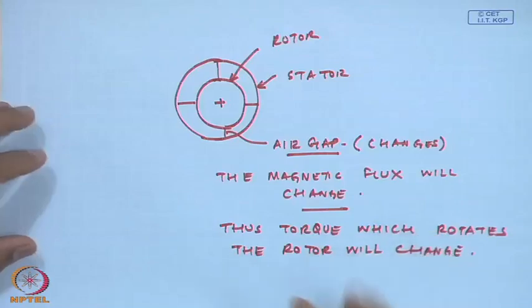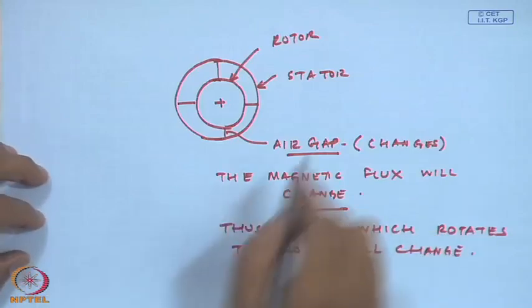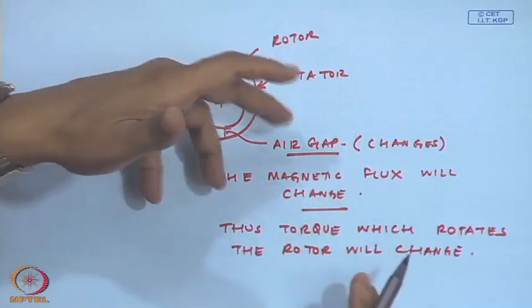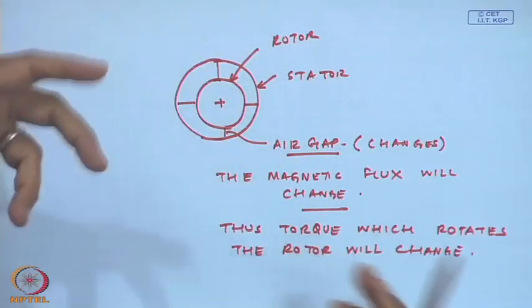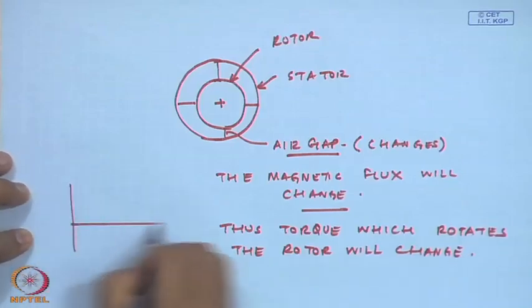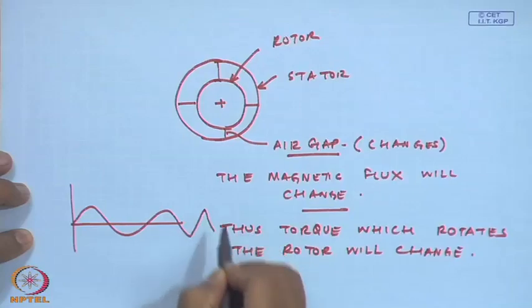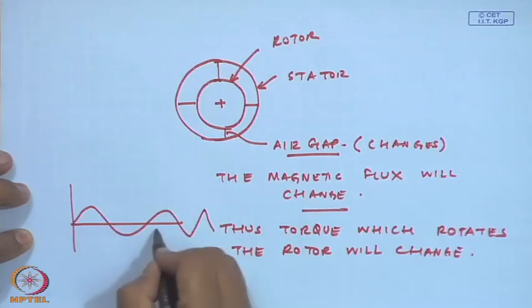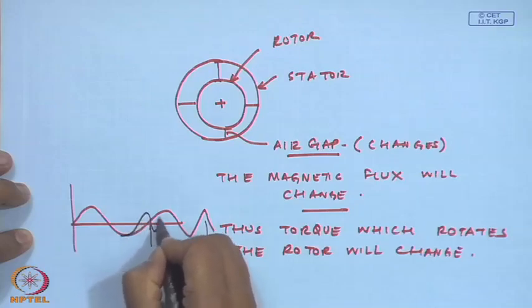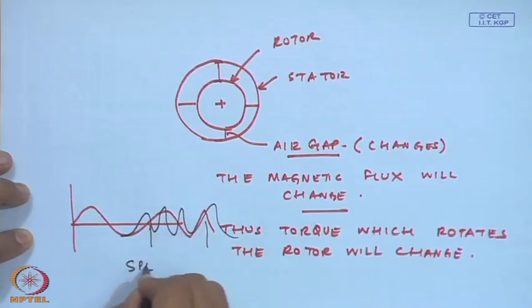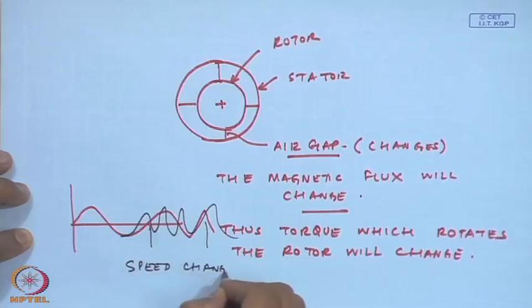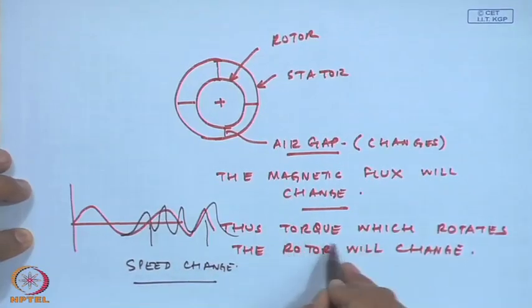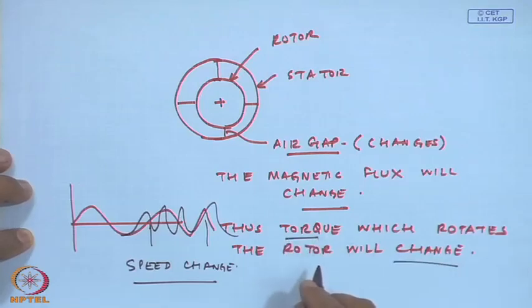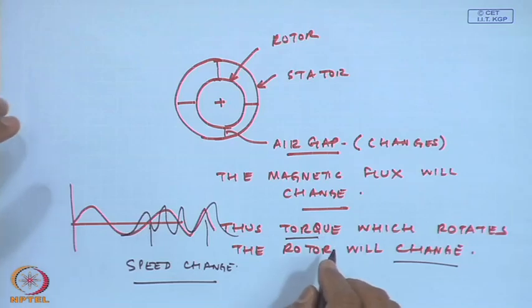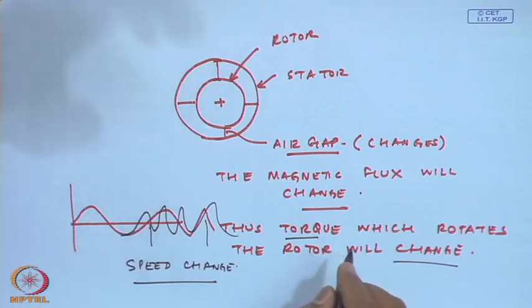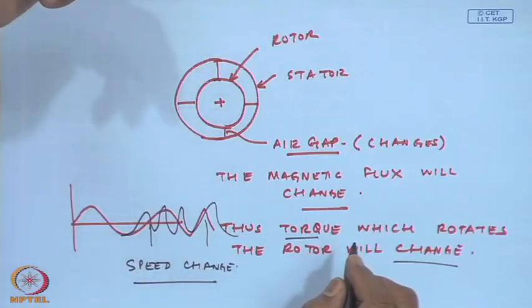So, many things would happen because of this. For some reason I have a different air gap, flux is going to change, torque is going to change. If torque changes, I will have a pulsating speed. This was supposed to have a uniform speed, but it may so happen that suddenly this spacing is going to change, and again pull up. So, speed change will occur. And torque changes mean your forcing function is no longer steady. The forcing function is changing, the dynamics is going to change. And over a period, if this goes unnoticed, this is going to be a fatigue load on the machine.